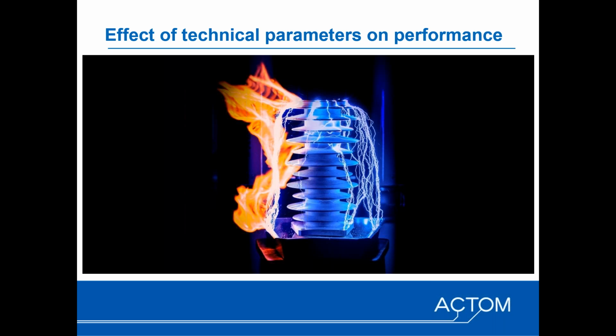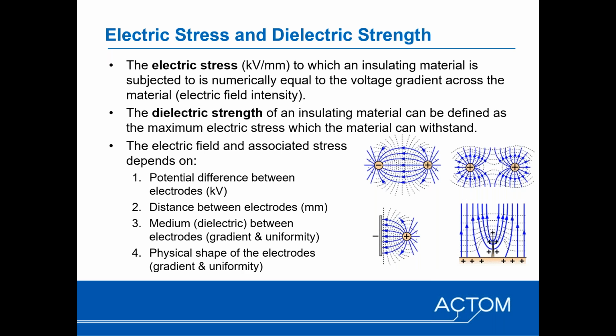Thank you, Red. Good morning, ladies and gentlemen. In order for us to understand and explain some of the technical details related to solid dielectric switchgear, we just need to review a few of the electrical principles that are applicable to the switchgear. In terms of electrical stress, when you've got voltage being applied between two electrodes, there's an electric field set up between those two electrodes, and the electric stress appearing in the gap between them is effectively numerically equivalent to the voltage gradient across that material. So where there's a high concentration of voltage gradient at electrodes, you will have a high stress concentration in that area.